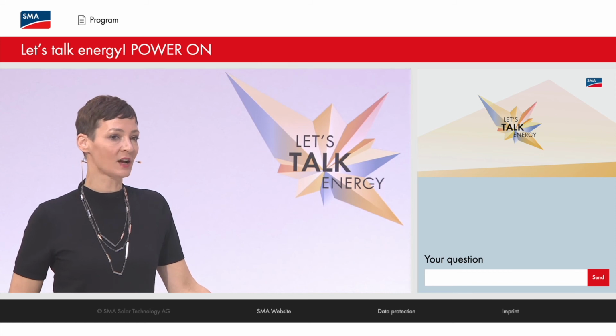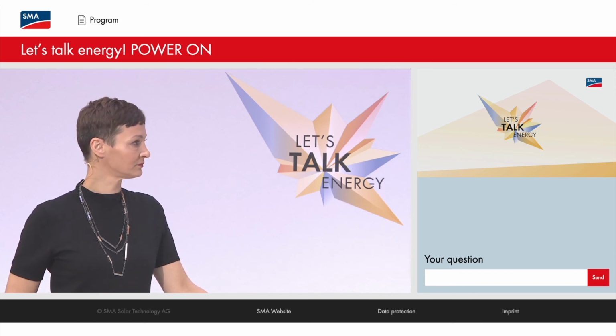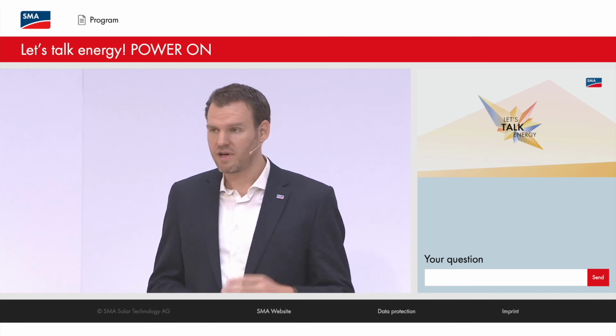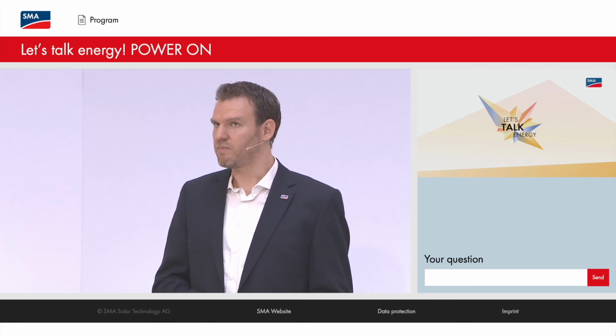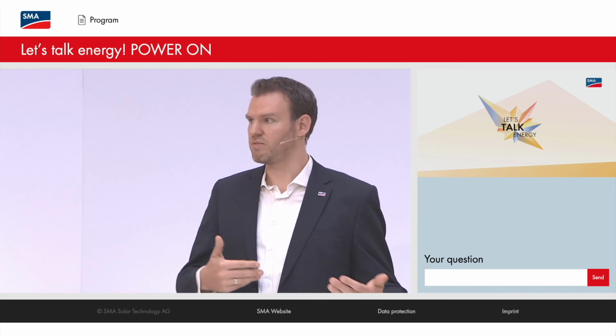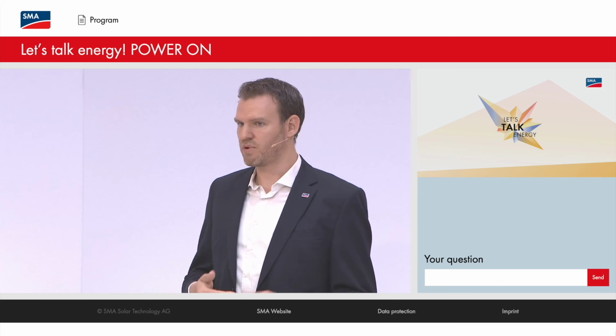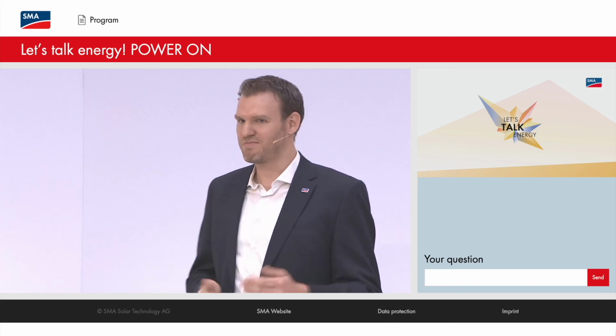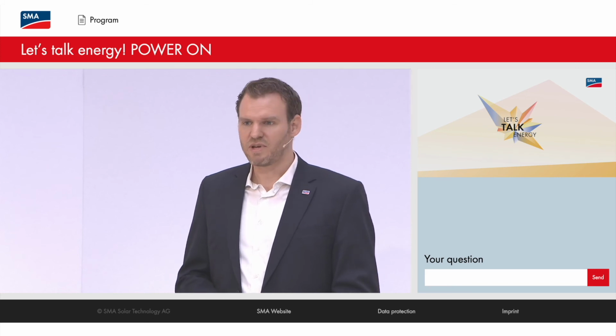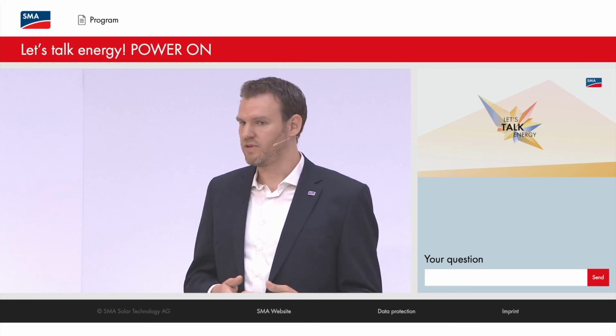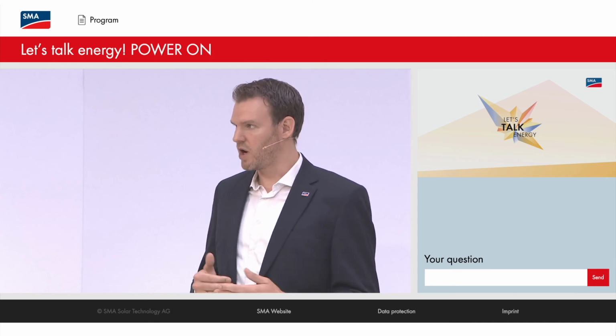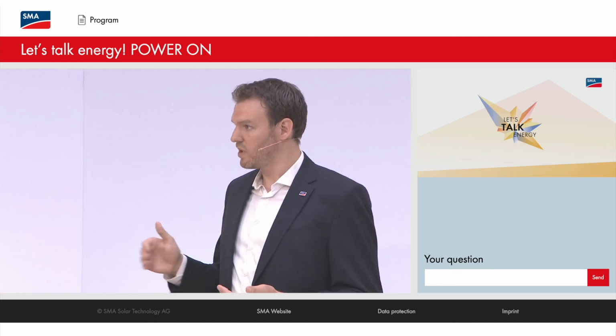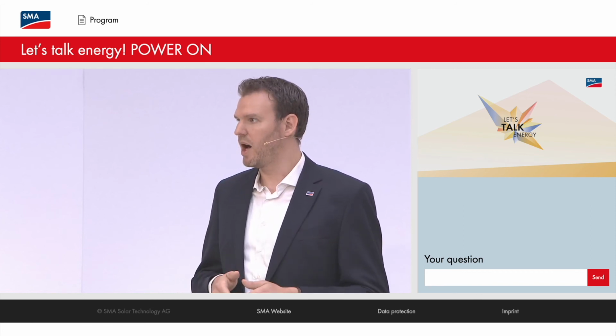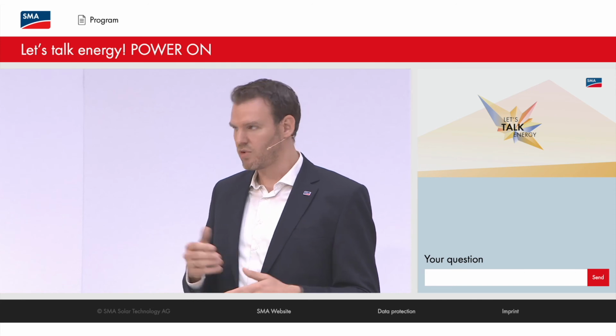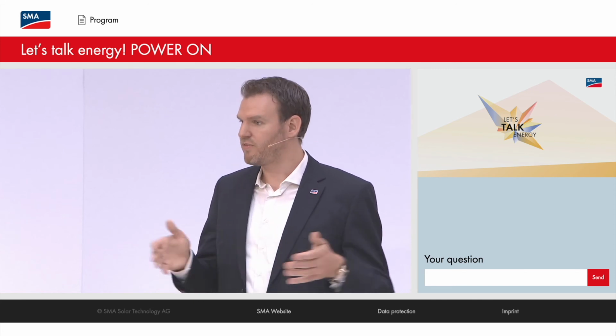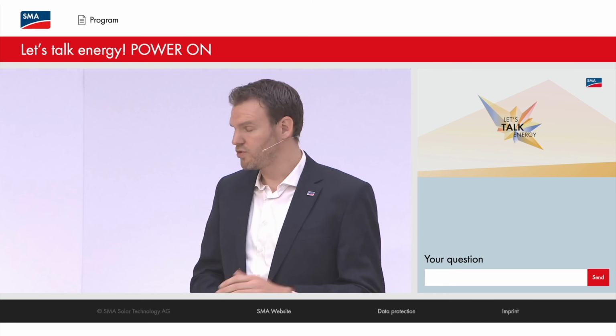The next one is, how do you promote storage in new markets, Carsten? Somewhat similar to my answer earlier. In some new markets, first it's important to understand what's actually the challenge in this market—what is the problem they have. Once you've understood the problem, you can propose a solution; if you don't know the problem, it's difficult to propose anything. We sometimes see that smaller countries, like we saw in Puerto Rico a couple of years ago, were adding storage to avoid ramp rate issues with rolling clouds. The storage closes the gap so that existing generation assets—gas turbines, diesel generators—can actually keep up with this fast movement. That could be a solution.